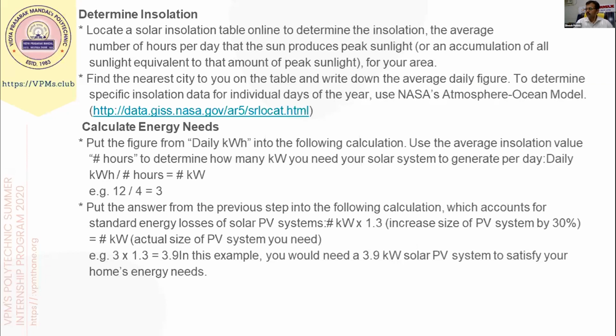Use the average insolation value, that is hours, to determine how many kilowatt hours you need your solar system to generate per day. Daily kilowatt hour divided by hours equals your kilowatt requirement. For example, 12 divided by 4 is a simple example I've taken - 12 is the kilowatt hour we want to use, divided by 4, the minimum insolation I consider here, so 4 kilowatt hours daily. If I install 1 kilowatt of system, 4 kilowatt hours is generated by solar.